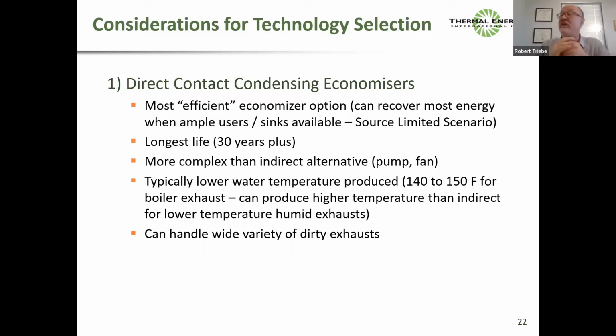So when we're spraying on the burner, and I'll get to your question first, in a natural gas boiler, let's start with natural gas, because of course your question can't be answered broadly; if you're burning dirty fuel, it's a different answer. With natural gas in a direct fired water heater, when the water passes once through, so I'm simply taking 100% fresh makeup, heating it to 180 F, 90 Celsius, once through, it's still potable water. And that's been determined through multiple tests. Natural gas is clean. We cook with natural gas at home. So in a one-pass system, the pH shifts by about 0.5. So it does get a little bit more acidic, but it still qualifies as potable and has been used in the food and beverage industry directly in process and sanitation with a direct fired unit, no issue.